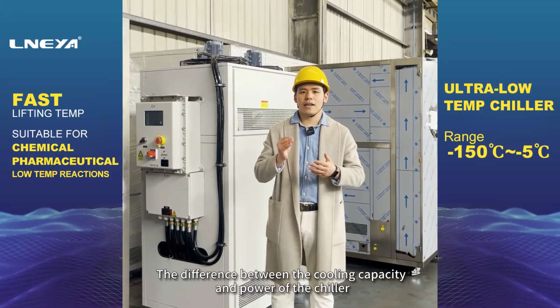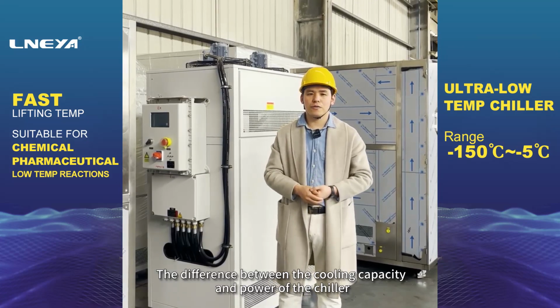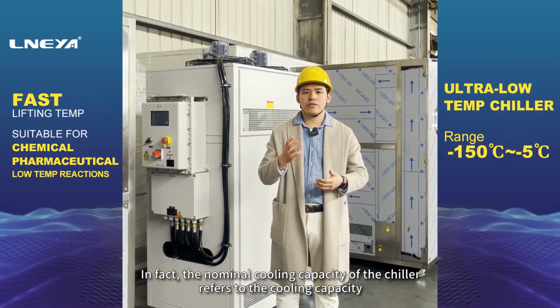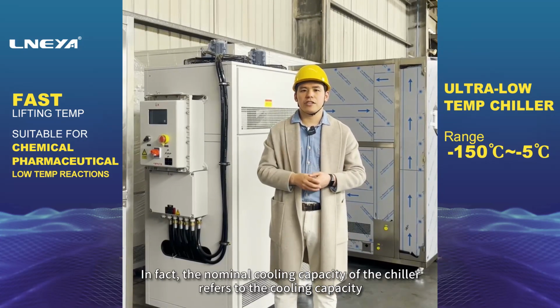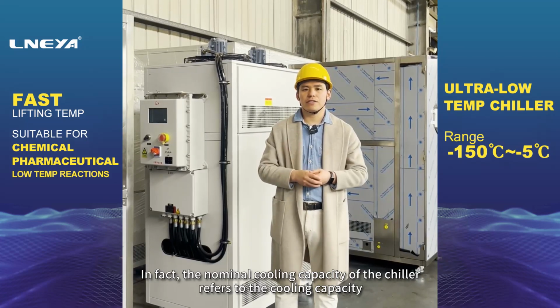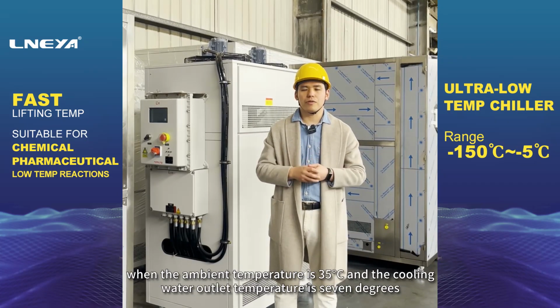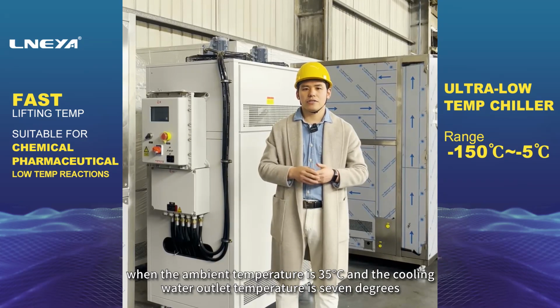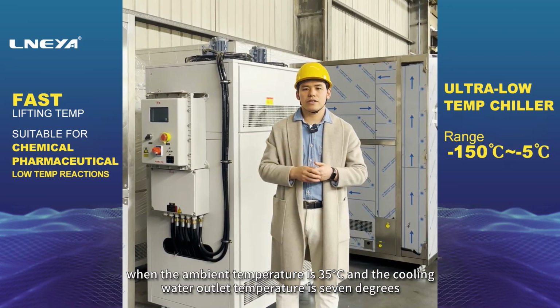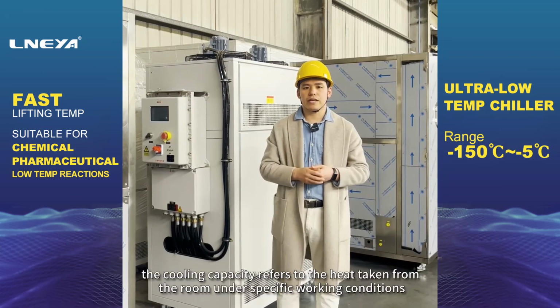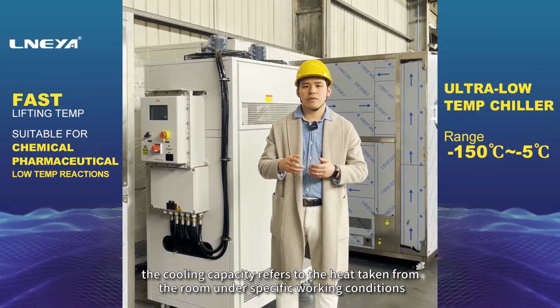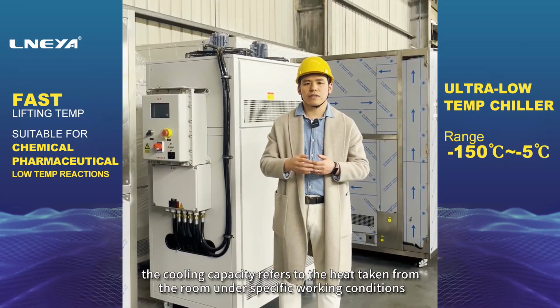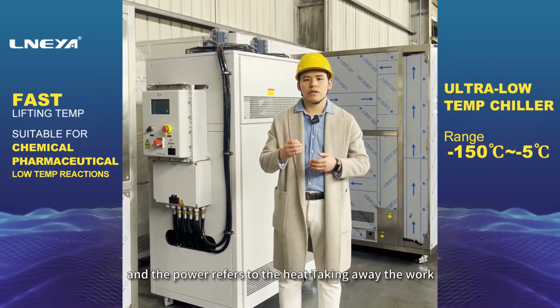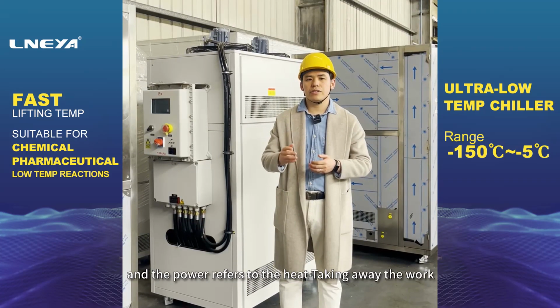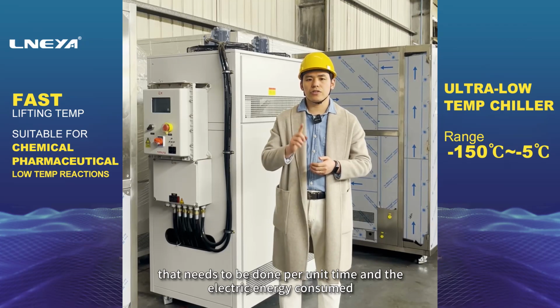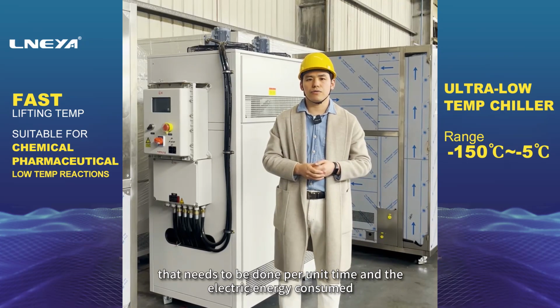The difference between the cooling capacity and power of the chiller. In fact, the nominal cooling capacity of the chiller refers to the cooling capacity when the ambient temperature is 35 degrees and the cooling water outlet temperature is 7 degrees. The cooling capacity refers to the heat taken from the room under specific working conditions, and the power refers to the work that needs to be done per unit time to take away the heat, and the electric energy consumed.